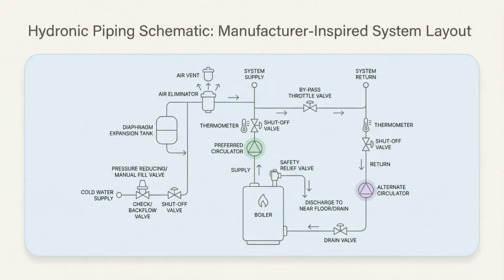Water piping is critical because wrong piping can damage the boiler or the building. Manufacturers warn about low flow and cool return water, especially on boilers not designed for it, and about oxygen contamination that drives corrosion. The piping layout also needs the safety relief valve and proper control locations, plus air elimination, expansion handling, isolation, and service drains, exactly as the manufacturer's piping drawing shows.